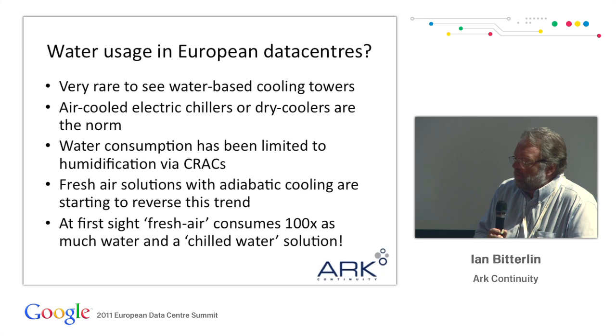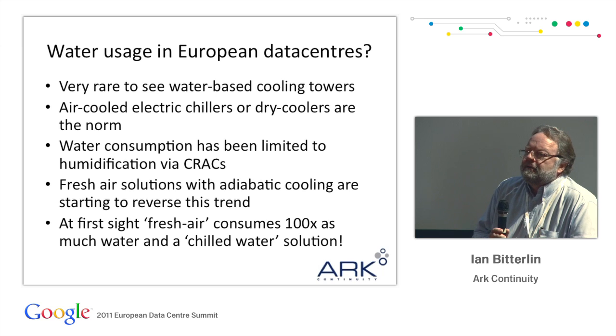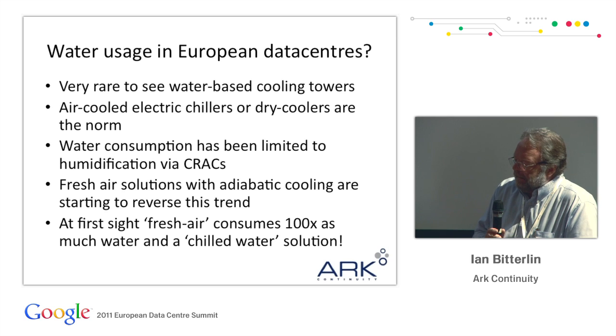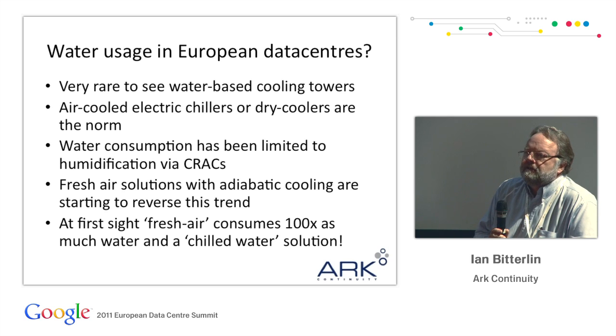Air-cooled electric chillers are the norm. Fresh air solutions with adiabatic cooling are definitely on the increase in terms of customer interest. But at first sight, those fresh air solutions consume 100 times as much water as our conventional chilled water solution, because we don't use cooling towers.